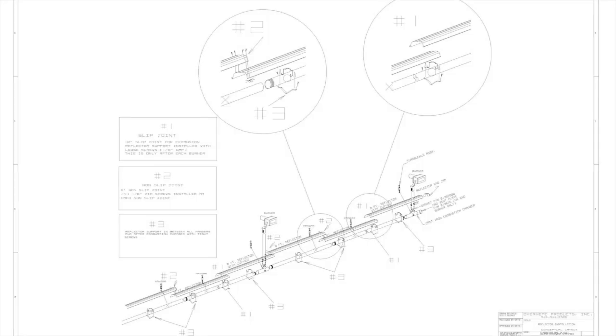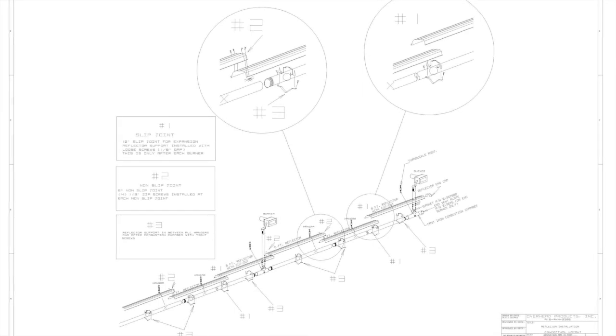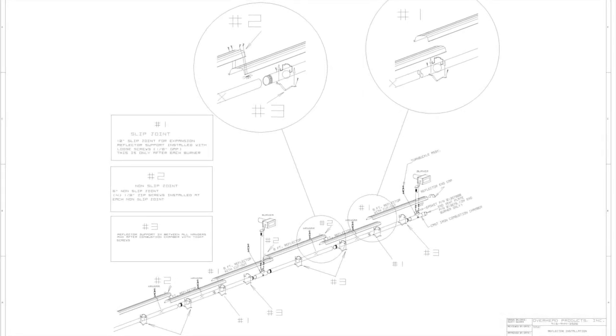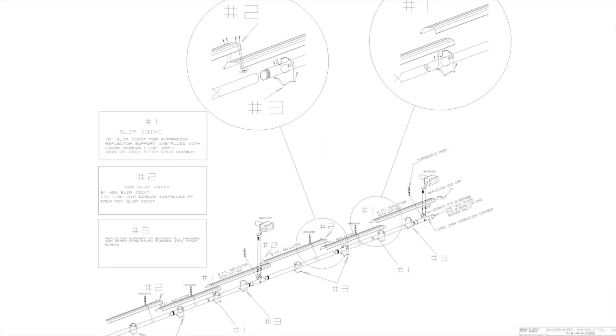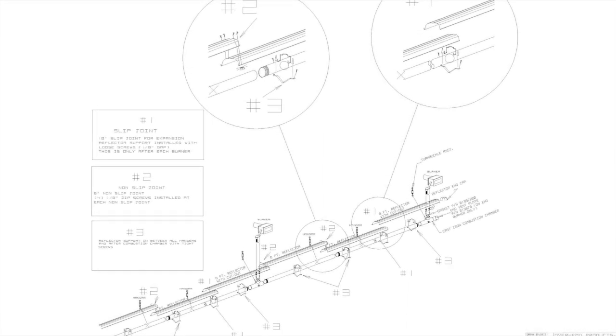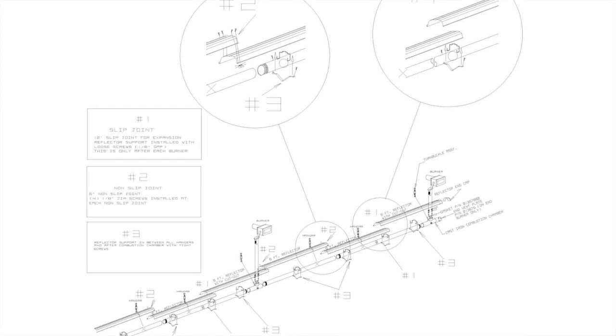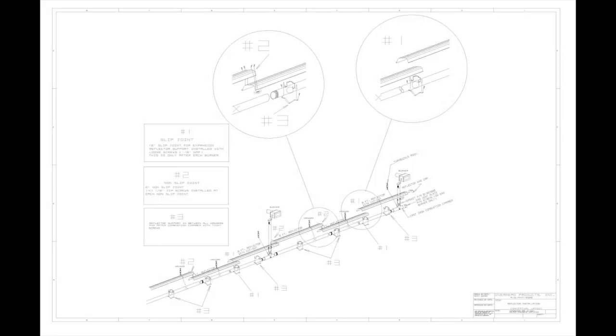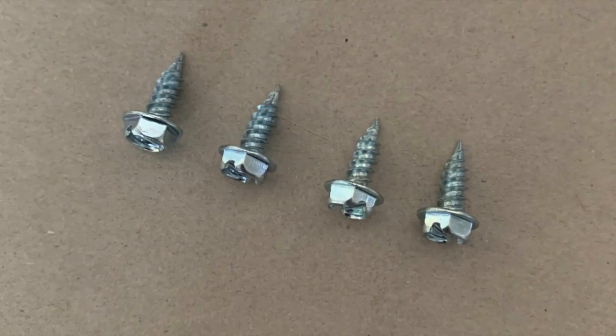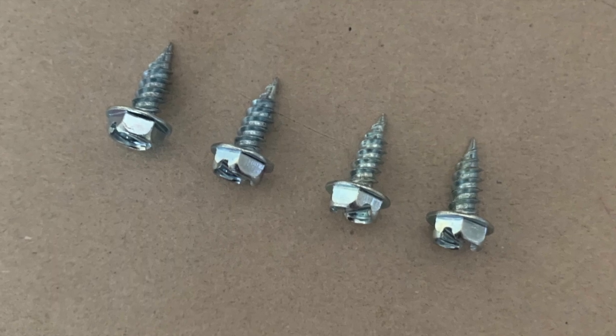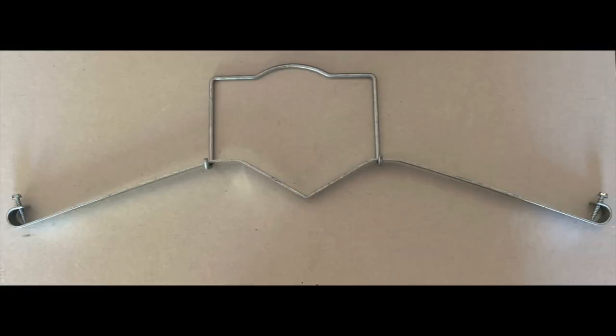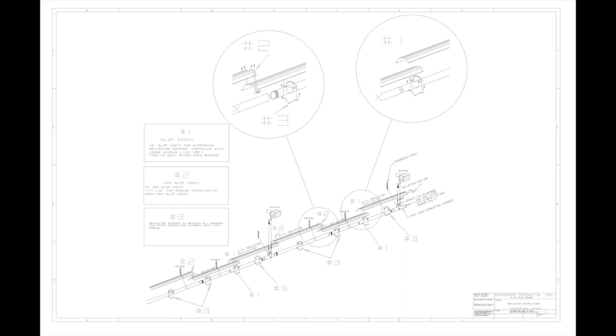The first overlap past each burner is an expansion joint. This overlap should have 1 foot overlap on top of the next reflector, with a reflector support in the middle of the overlap with loose screws in the reflector support and no screws in the reflector. All other overlaps of the reflector should be 6 inches in length and have 4 number 8 zip screws securing the reflectors. In between all hangers, there will be a reflector support with tight screws in the reflector support. This is shown in the conceptual drawing provided in the submittal.